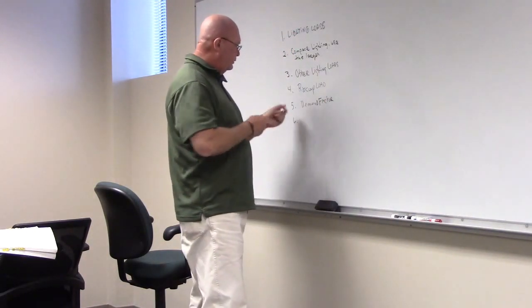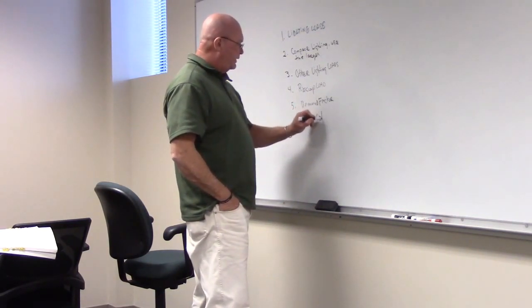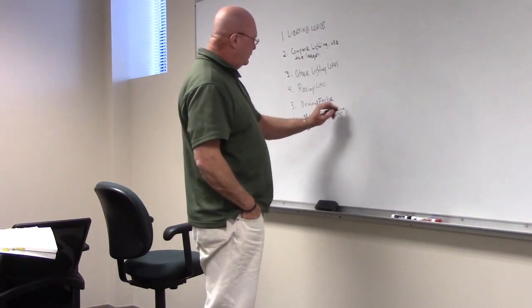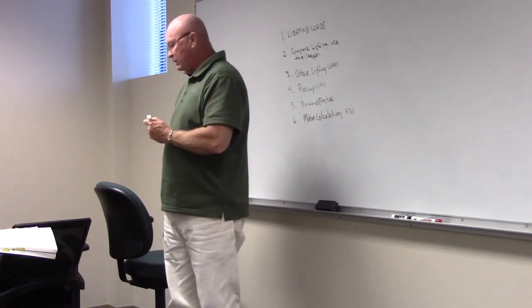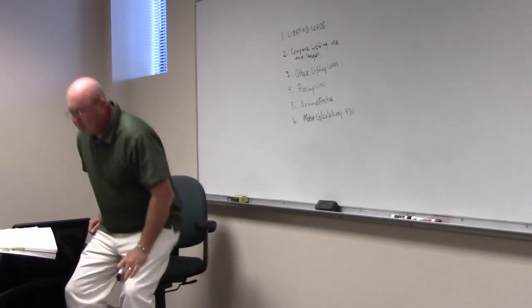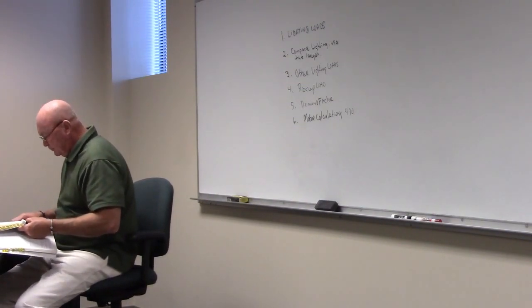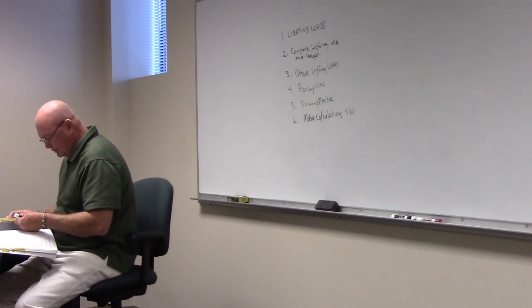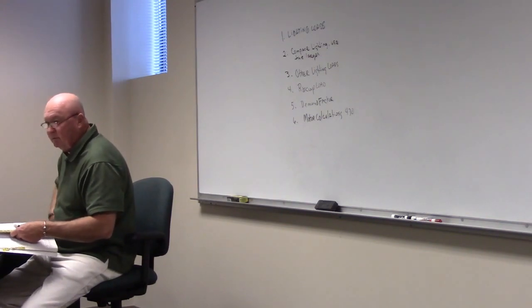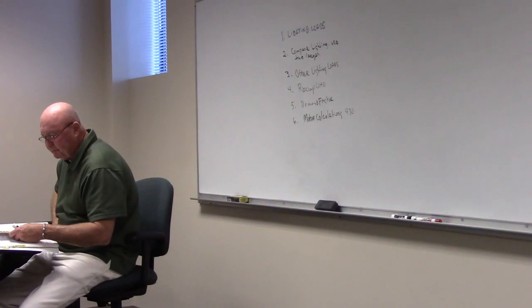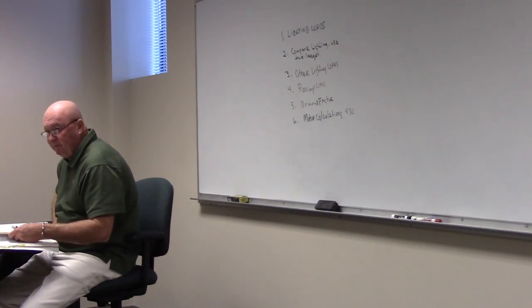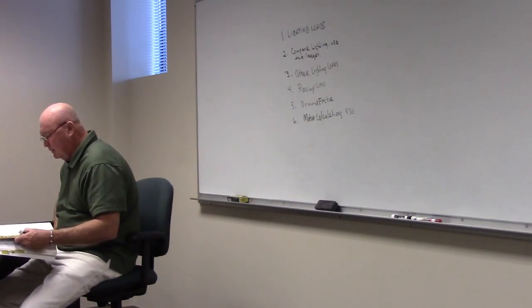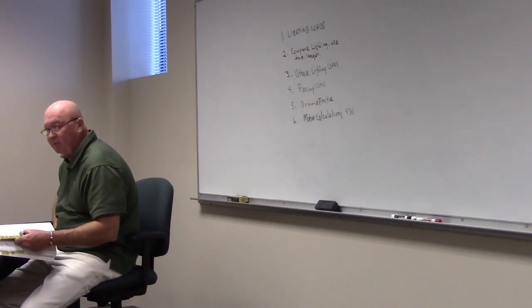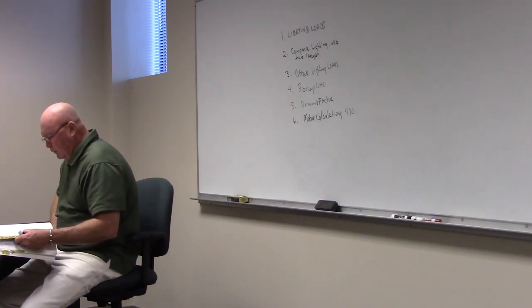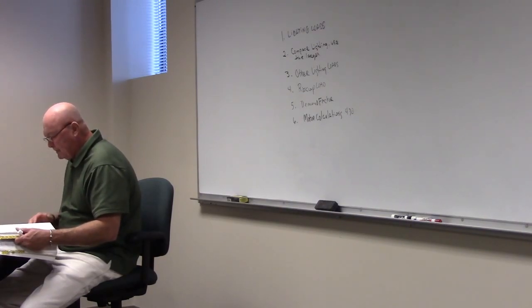So step number 6 is motor calculations. Motor calculations are found in the code book. What section? 430. Anytime you get a question, matter of fact, let's turn over to 430 right quick. 430.248, I think, is where we want to go. Table 430.248 is amperage for single-phase motors. Table 430.250 is amperage for three-phase motors. That's 2 tables that you need to remember. 430.248 is for single-phase, 430.250 is for three-phase. You remember those 2, you got it booked.